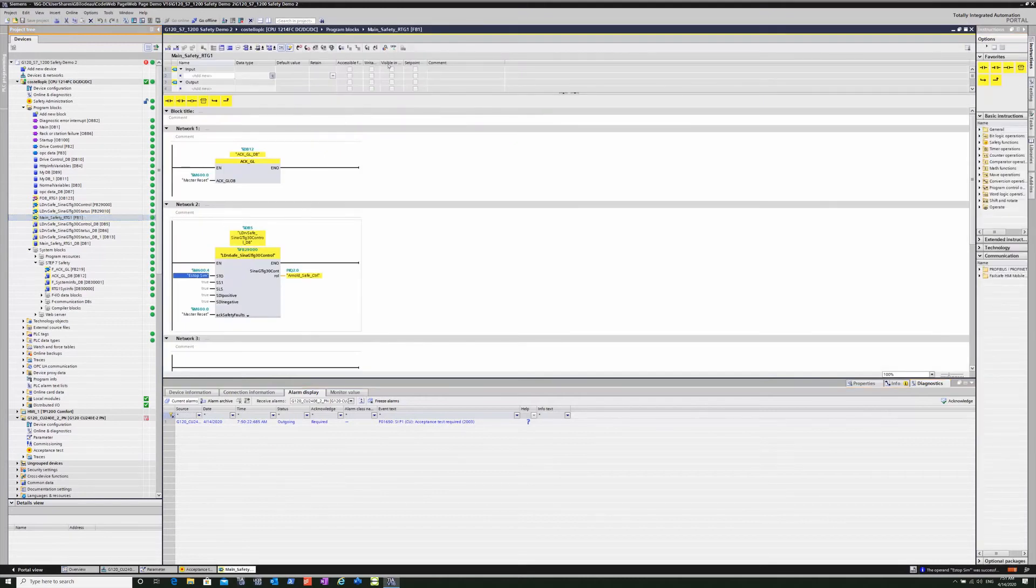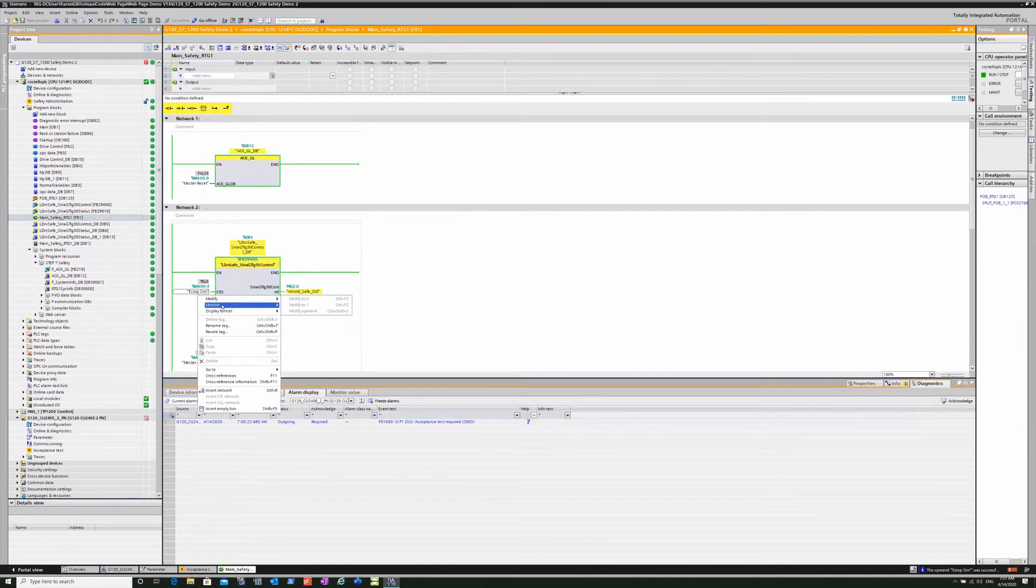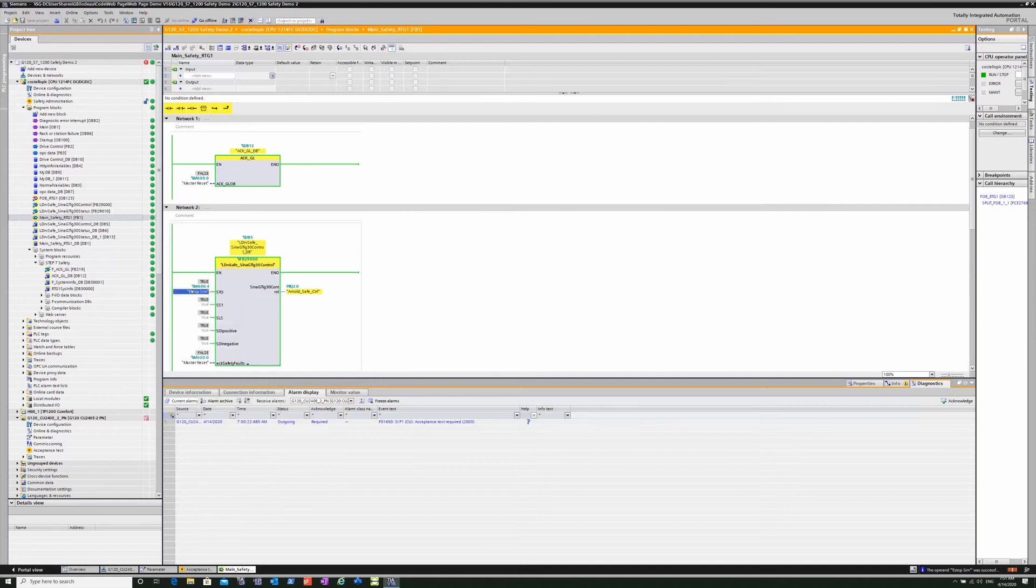So there's the STO active is off, which means the drive is not e-stopped anymore. And the yellow light on the drive will go solid yellow instead of flashing.